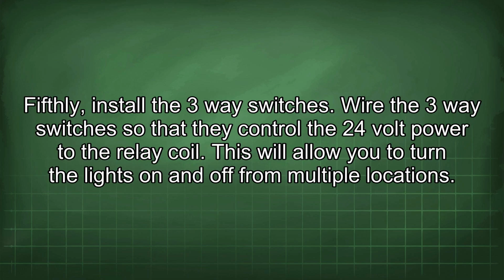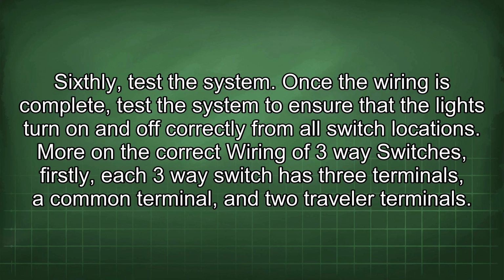Fifthly, install the three-way switches. Wire the three-way switches so that they control the 24-volt power to the relay coil. This will allow you to turn the lights on and off from multiple locations. Sixthly, test the system. Once the wiring is complete, test the system to ensure that the lights turn on and off correctly from all switch locations.